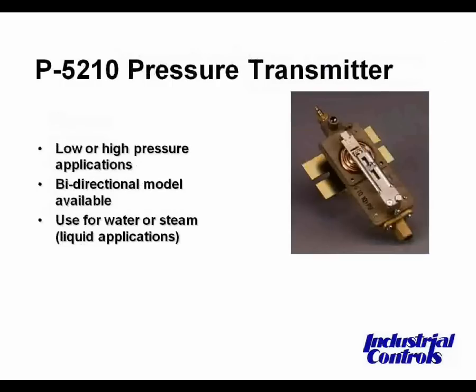Next is a pressure transmitter. This can be used in high or low-pressure applications. There are even some bi-directional models available that can be used for water, steam, or air pressure applications. It looks very similar to what we've seen before, but the air connection for main air to the transmitter is at the top at the barbed connection. The bottom connection is a 1/8-inch NPT pressure connection for whatever condition is being measured — air, steam, or water.